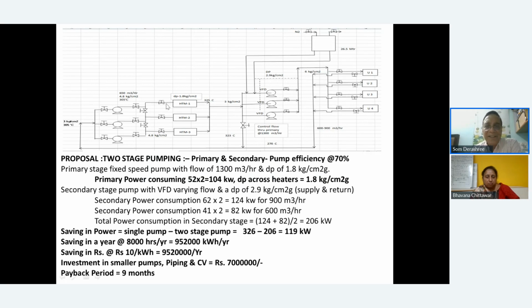But here the requirement is 650 always. So what happens is, here there's no VFD. It is simply circulating. So your head pressure has gone down, and accordingly, if you see, almost 119 kilowatt of power saving. This is almost close to about 95 lakh units, and the modification for pumps extra is another 70 lakh. So less than a year is the payback period.